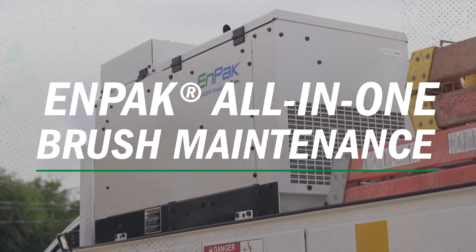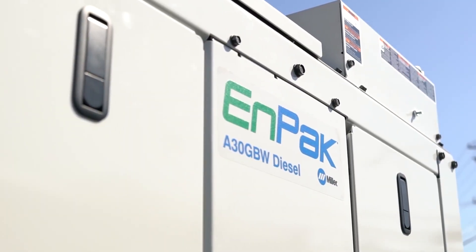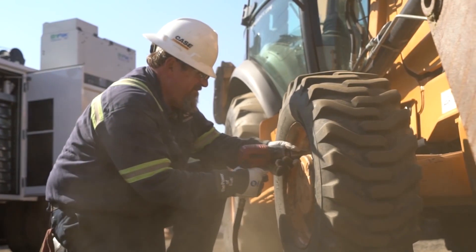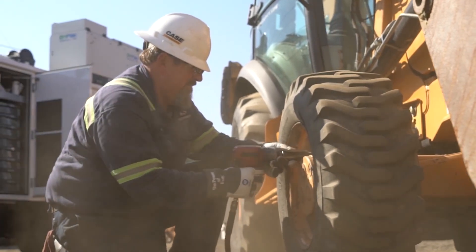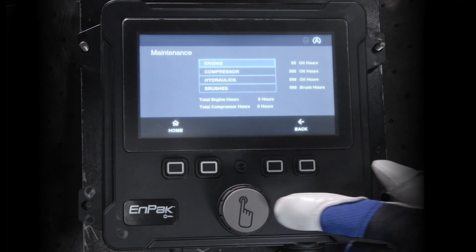Don't overlook brush maintenance on your EnPak A60 and EnPak A30 power system. Generator brushes carry the current that maintains the magnetic field strength to produce proper generator output. Brushes should be changed every 1,000 hours to avoid failure and costly repairs.